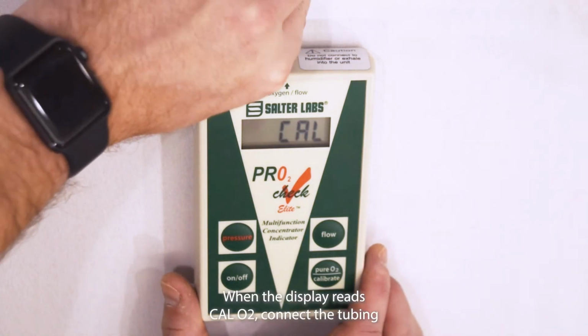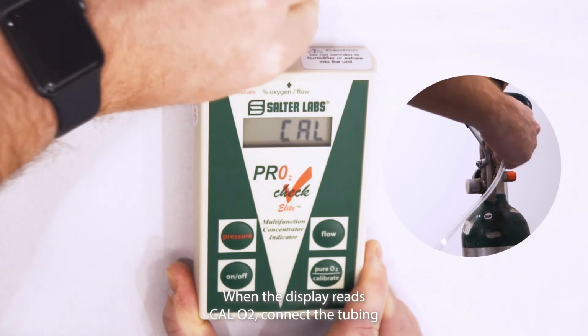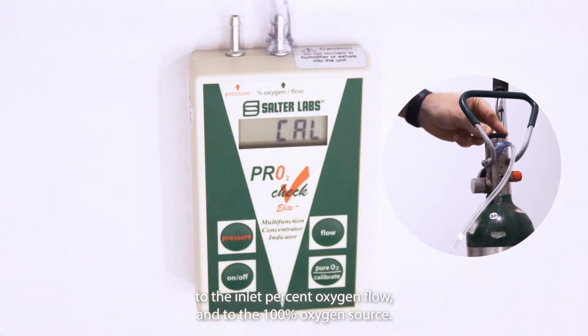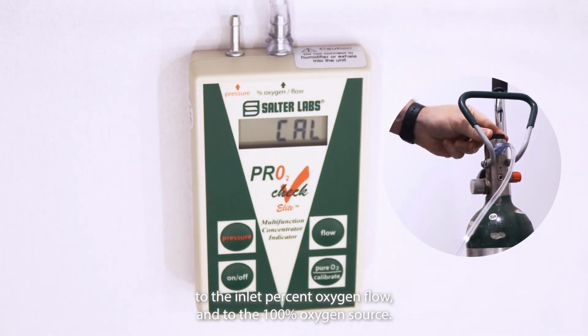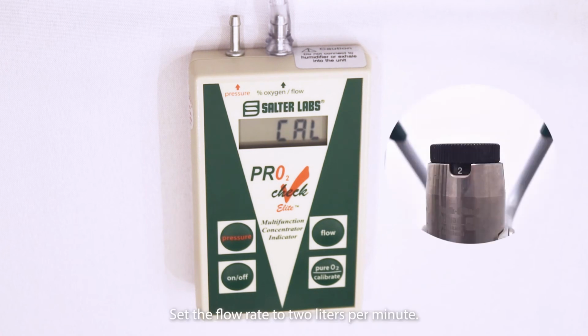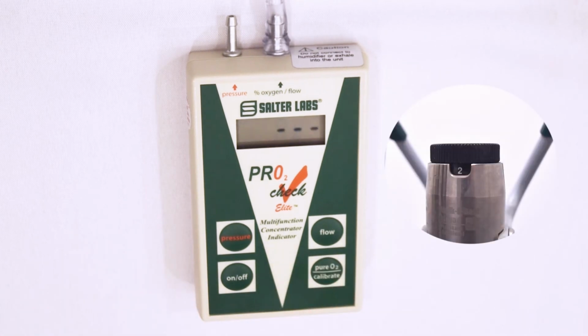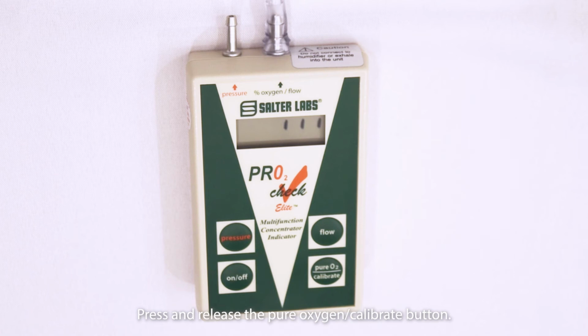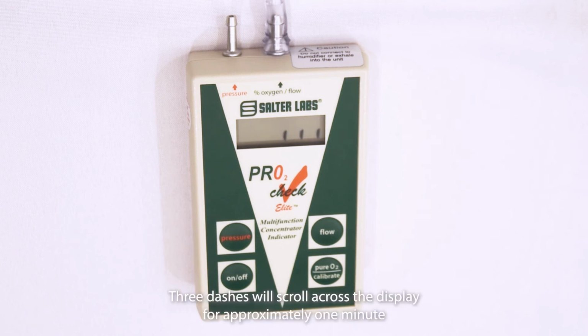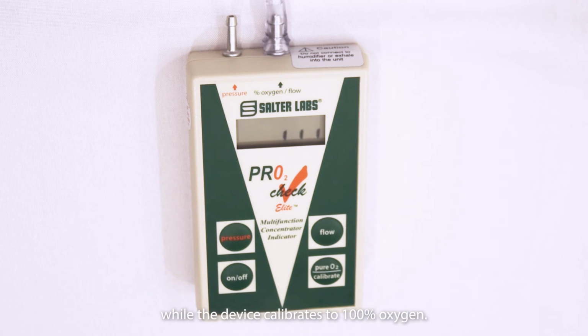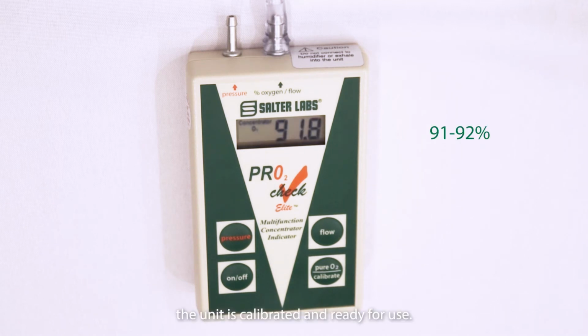When the display reads Cal Oxygen, connect the tubing to the inlet percent oxygen flow and to the 100% oxygen source. Set the flow rate to 2 liters per minute. Press and release the Pure Oxygen Calibration button. 3 dashes will scroll across the display for approximately 1 minute while the device calibrates to 100% oxygen. When the display reads Cal End and 91 to 92%, the unit is calibrated and ready for use.